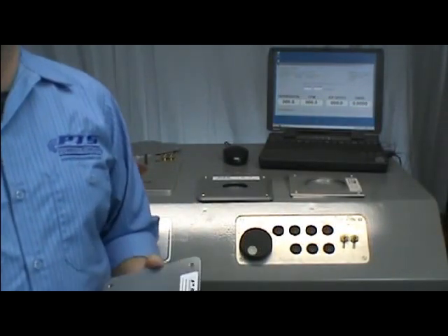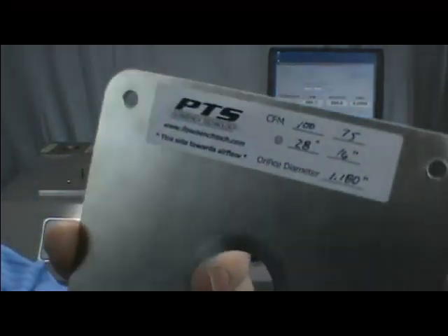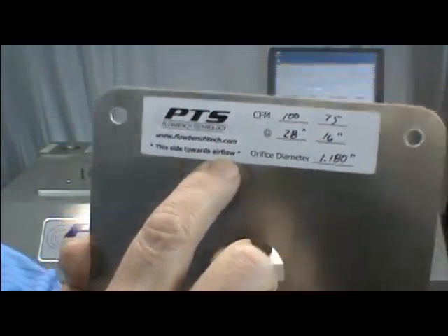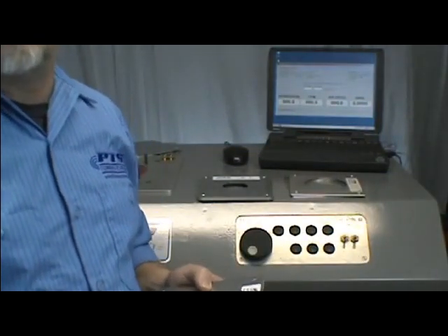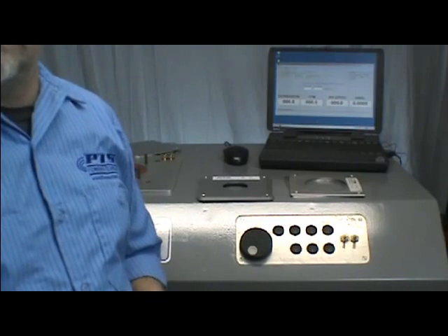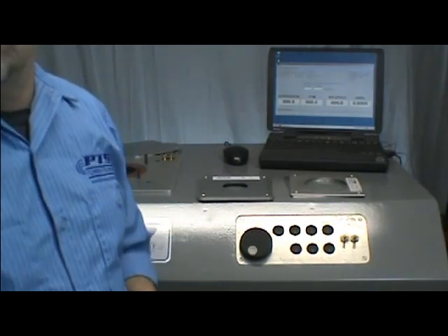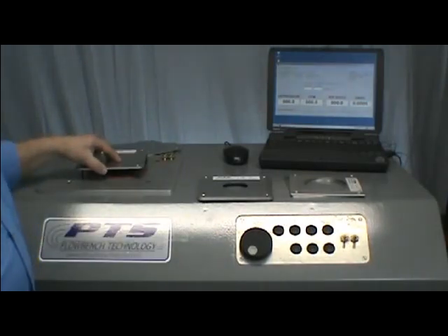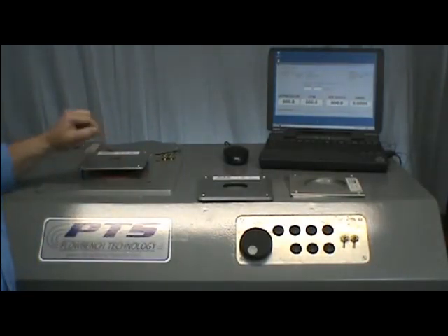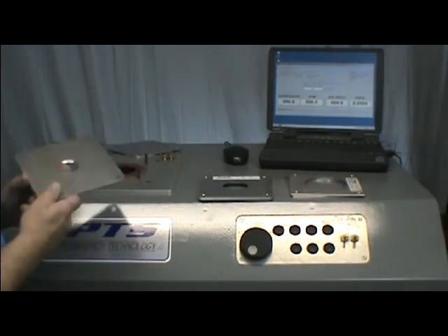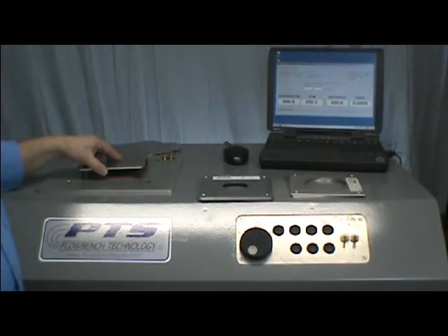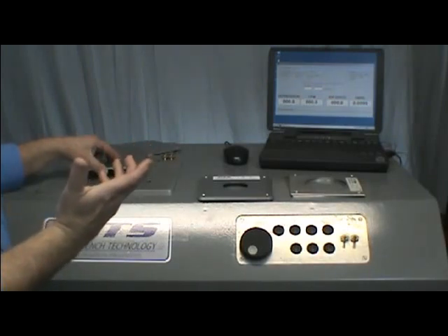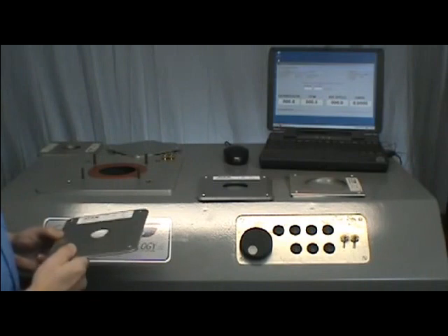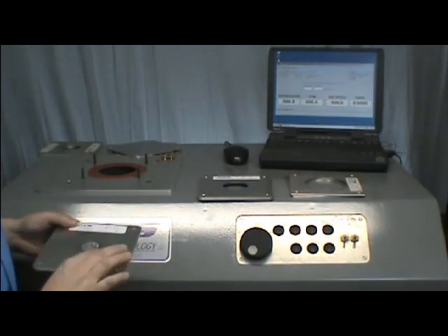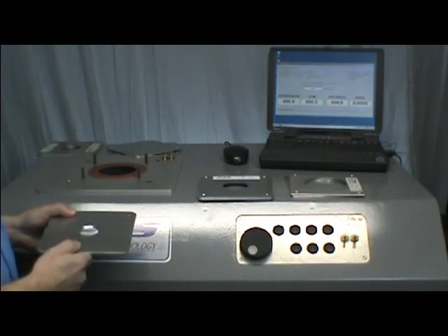Sharp edge orifice plates do have a top and bottom. As you will see on the label, it says this side towards airflow. Some of my earlier plates that are out there in the field do not have that on the label. But in the intake mode, on top of the flow bench, the label will always face up. In exhaust mode, you flip the plate over and it faces down. Again, the airflow is coming towards the face of the plate, and that's the way you want it. When it's inside the flow bench, it's exactly the same way. Label up on intake, label down in exhaust mode.